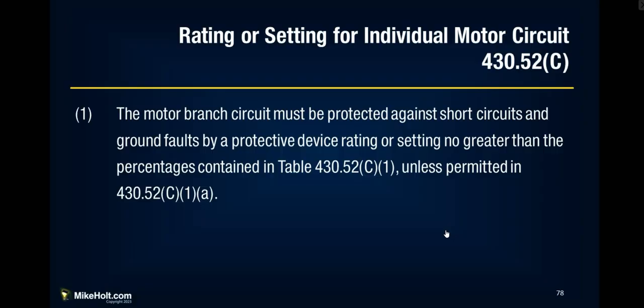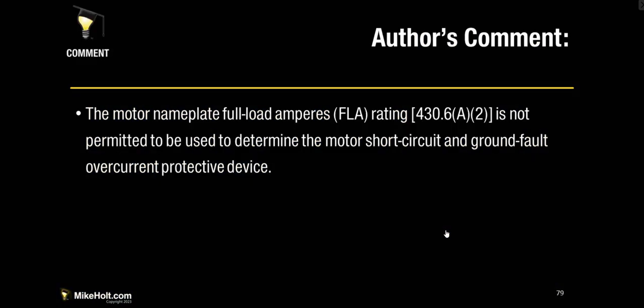And the motor branch circuit must be protected against short circuits and ground faults by a protective device rating or setting no greater than the percentages given in the table I was just telling you about, 430.52. The FLA rating is not permitted to be used to determine the motor short circuit and ground fault overcurrent protective device. And hopefully you can see that, to where most people would go, oh, I got this motor. Look, there's a nameplate on it, and it says what the ampacity is. That's not what you would size your overcurrent protection on. How many times do you think that mistake gets made?